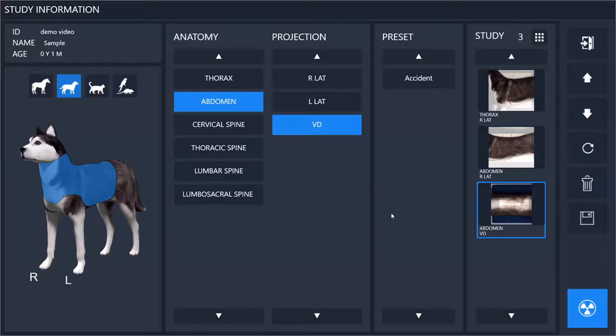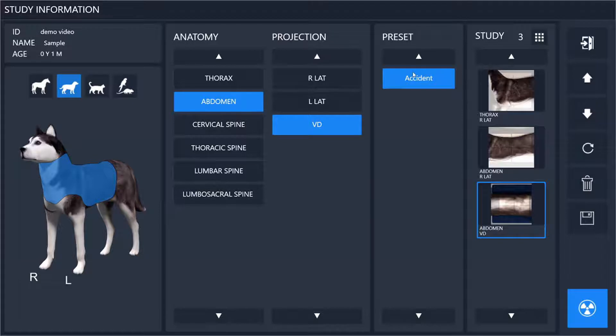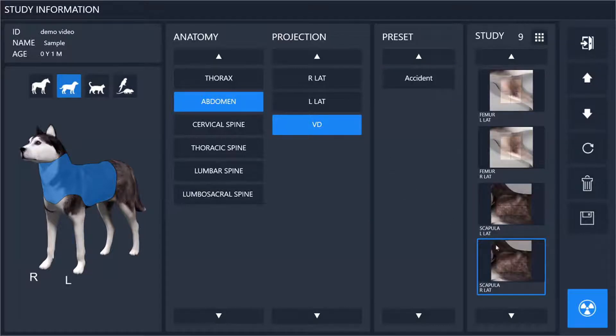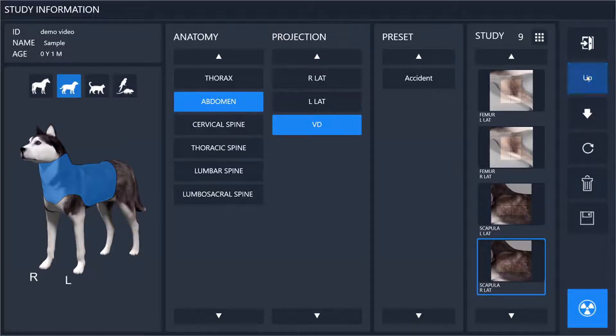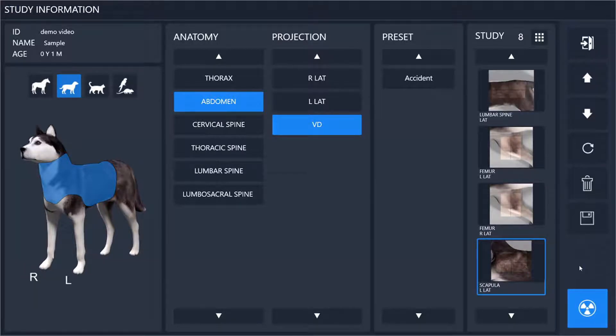You can also create preset exams. These are exams where when you click on a single button it will fill in multiple X-rays for you, so you don't have to repeatedly enter your most common exams. You can see here it created two femurs and scapula entries for an exam that somebody might have gotten into an accident. You can move them around, delete unwanted ones, and arrange all of your planned X-rays in the exact order you're planning to do them — that will make life easier when you click exam and start your actual X-rays.